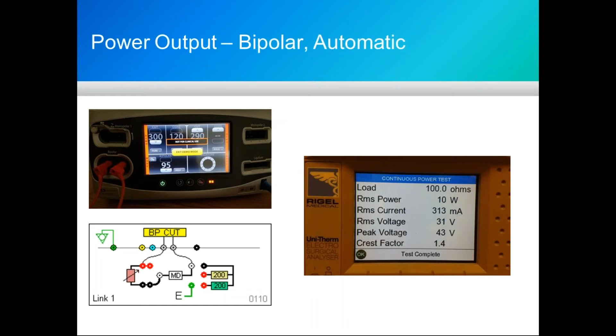And here's for bipolar. It's a little bit different for a setup. You can see on the picture the representation of what the side of the Unitherm will look like. It'll come from both the cuts. They'll both be active probes going into the unit. And you can see on the picture on the FT10 where the leads are connected. And the picture on the right-hand side is the actual output. So this is where you'll see the mA and be able to record it and see if it's within the tolerances.